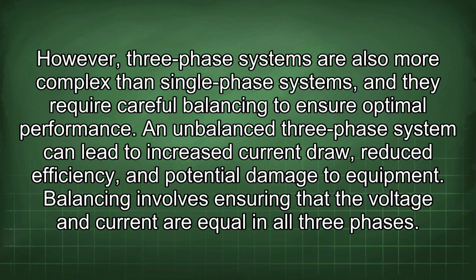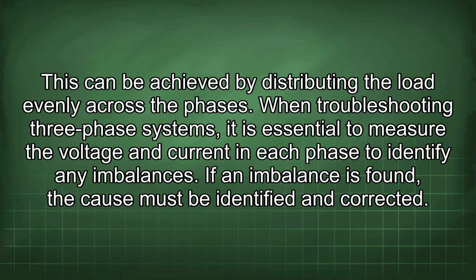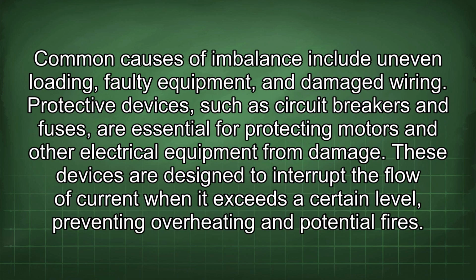An unbalanced three-phase system can lead to increased current draw, reduced efficiency, and potential damage to equipment. Balancing involves ensuring that the voltage and current are equal in all three phases. This can be achieved by distributing the load evenly across the phases. When troubleshooting three-phase systems, it is essential to measure the voltage and current in each phase to identify any imbalances. If an imbalance is found, the cause must be identified and corrected. Common causes of imbalance include uneven loading, faulty equipment, and damaged wiring.